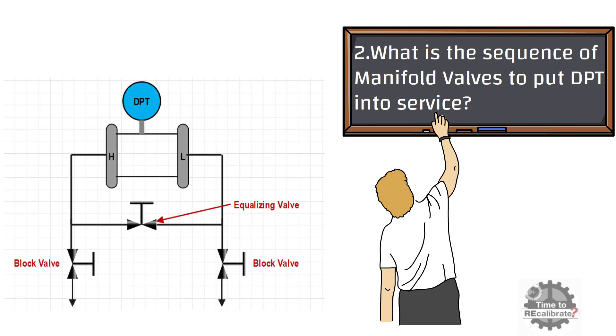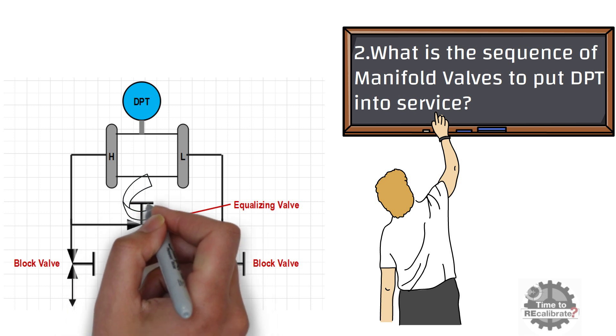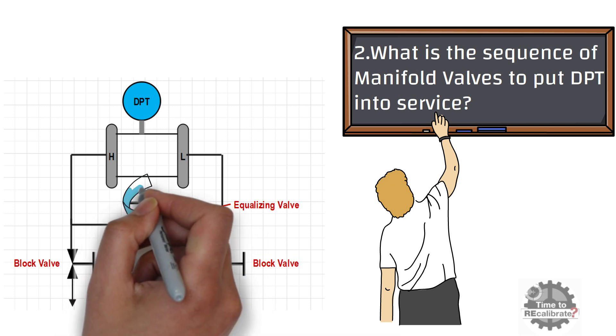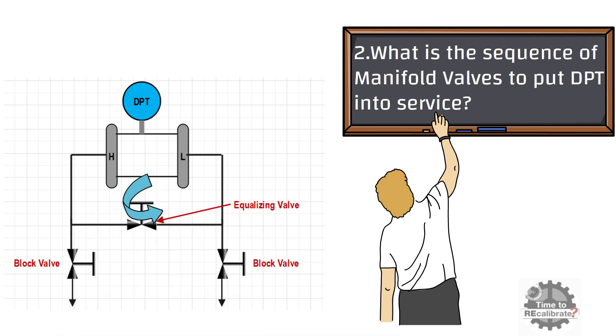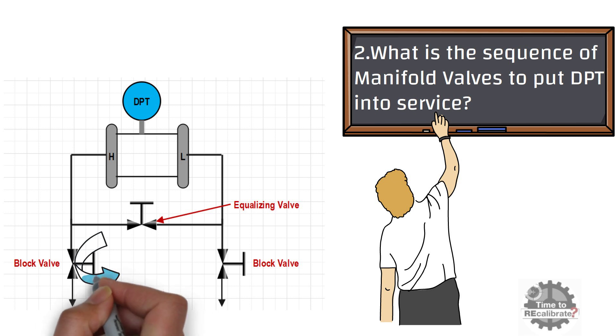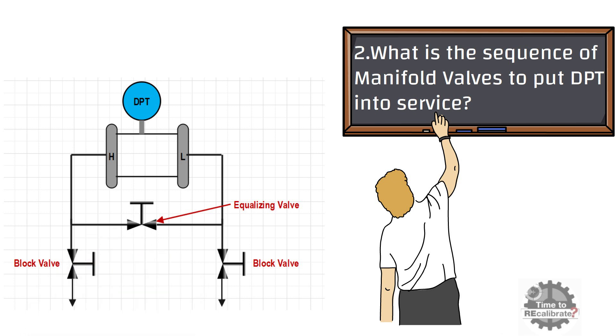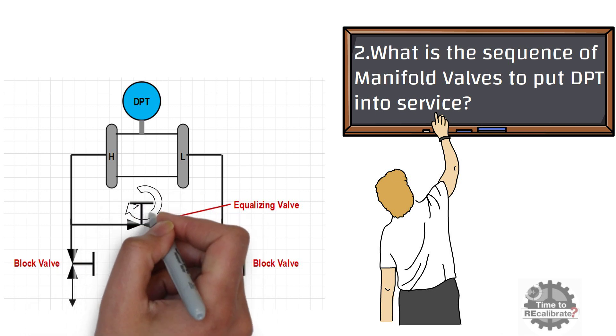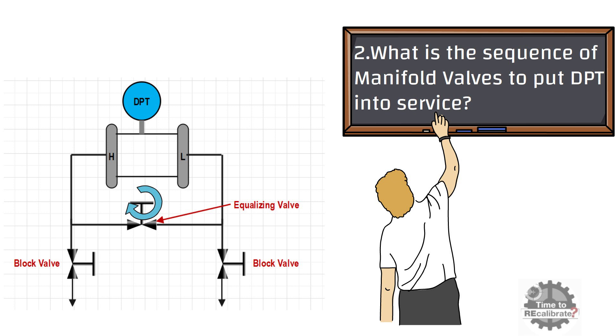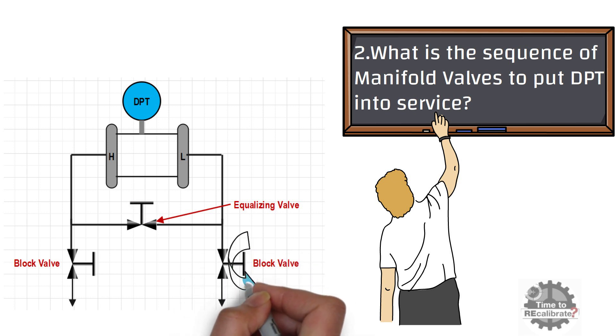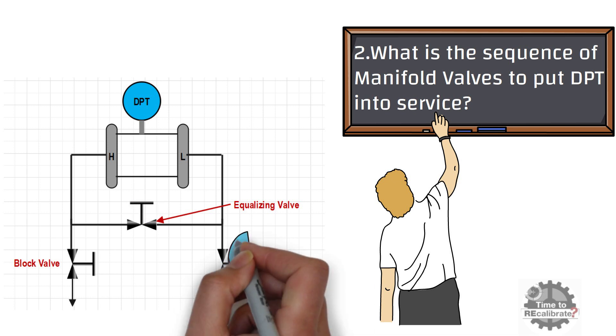To begin with all valves in a closed position, first of all open the equalizing valve. Then open the high pressure block valve slowly. Then close the equalizing valve. And finally, open the low pressure side block valve.